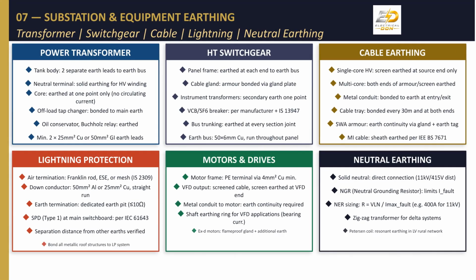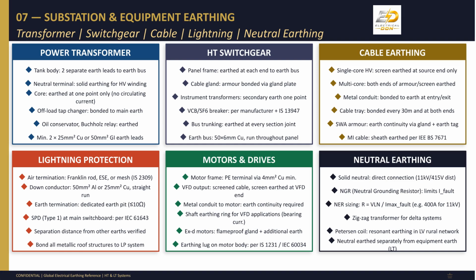For power transformers, neutral earthing is solid for HV windings, and tank and core earthing must be separate. HT switchgear earthing ensures all panel frames and bus trunking are bonded. Cable earthing practice depends on core type. Lightning protection requires dedicated earth pits. Neutral earthing methods vary, using solid, NGR, or zigzag transformers.